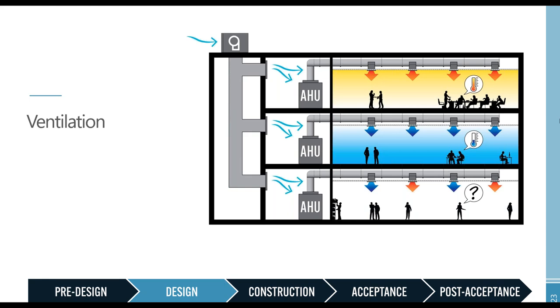So raw outside air, hot and humid during the summer, frigid during the winter, is delivered directly to the mechanical room via these risers that run the height of the building. The outside air is then mixed with return air and treated by the air handling units located in the mechanical room. The ventilation system project was technically outside the scope of our retrocommissioning project. However, as it was happening simultaneously with our other testing in the building, we wanted to weigh in on the design. So dampers were to be installed in each mechanical room. The sequence called for them to open and close based on whether or not the air handling unit was enabled.